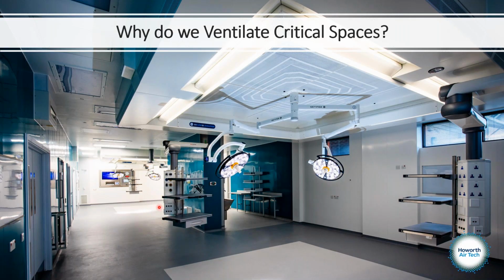If you look at HTM 03-01 Appendix 10, it gives you a cause and effect. When you do a barn theatre, you need to look at the cause and effect of what happens if this barn down here, if the fans trip or the PD panel trips and it goes off, does this patient still remain protected from the outside environment whilst they're still open having orthopedic surgeries being undertaken on them? Everything that you can see in that picture was supplied by Howorth through our package and our capitals team, and we still service that to this day. That's at Airedale Hospital in Yorkshire.